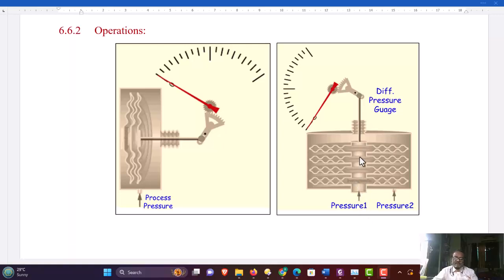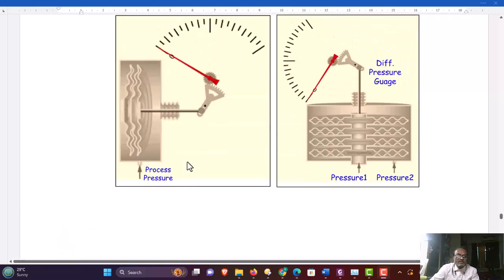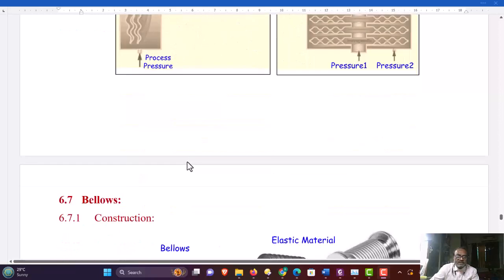Whenever the pressure increases, the capsule elongates, and due to that, the moving end pushes the rod up. When this rod goes up, the gearing arrangement moves the pointer on the scale. The applied pressure is converted to a proportional deflection on the scale. A differential pressure gauge can be used for measurement of pressure with respect to atmospheric pressure, whereas absolute pressure transducers or absolute pressure gauges can be used to measure the pressure with respect to absolute zero pressure, and this is one of the applications of the capsule type of pressure transducer.